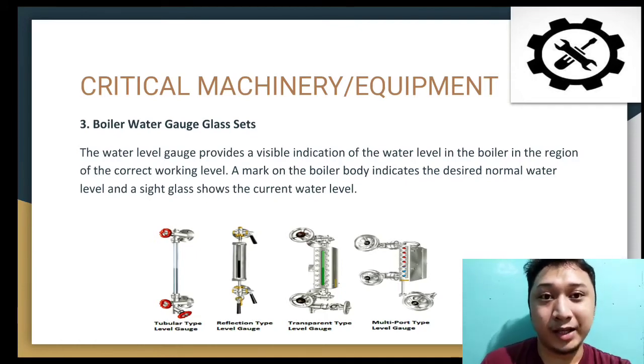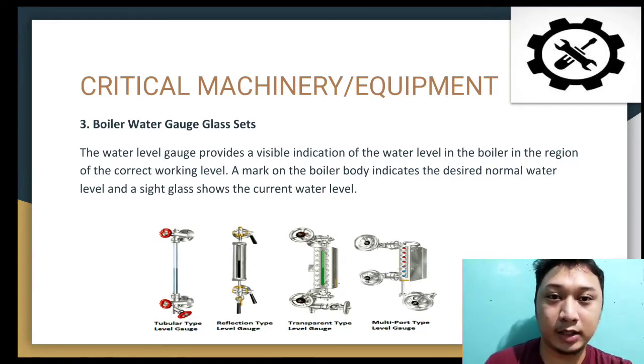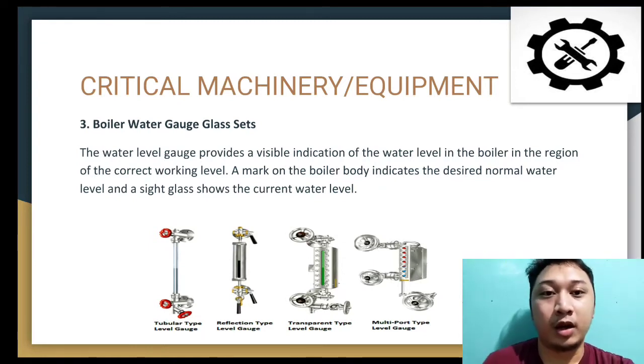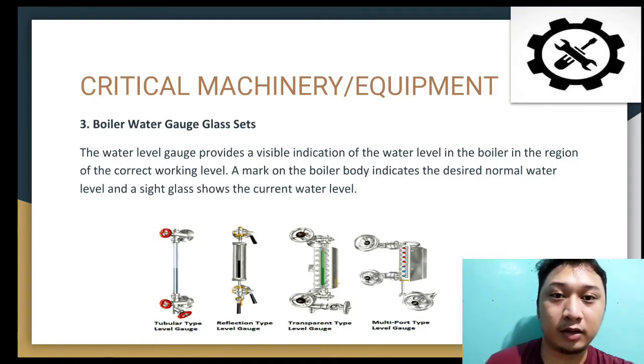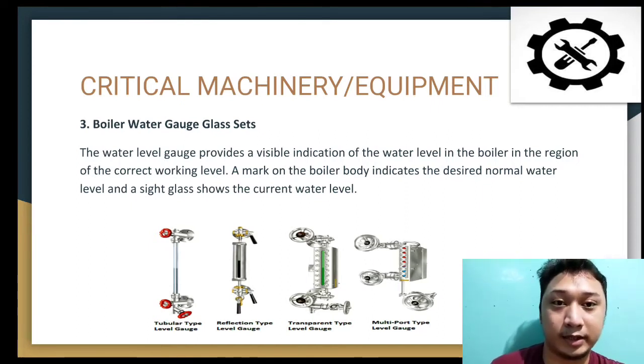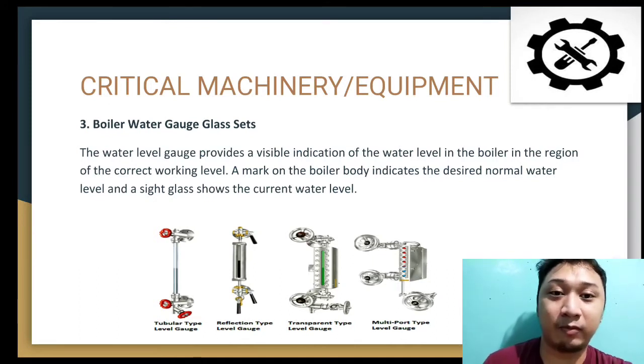So basically, we can say that the boiler water gauge glass set is very critical machinery because the gauge glass on a steam boiler enables the operator to visually observe and verify the actual water level in the boiler. But water stains and clogged connections can result in false readings. The glass also may break or leak, so it takes time to replace the glass, even if the boiler must be shut down. As you can see in the PowerPoint slide image below, the first image is the tubular type level gauge.